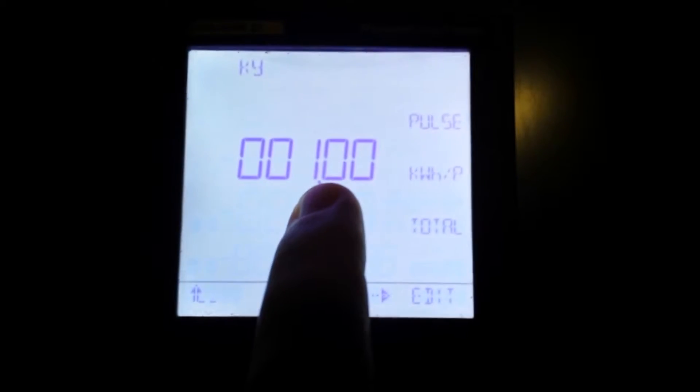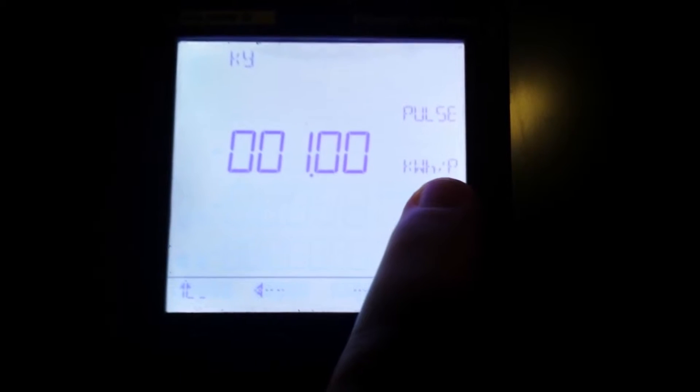Now that we have our password entered, we're going to scroll over until we reach the IO setup, which is right here. This is what we're wanting - we're using the output from this meter, so I'm going to press IO. I'm going to press out because we're looking for an output. Now then, it is currently configured for pulse at one pulse per kWh.